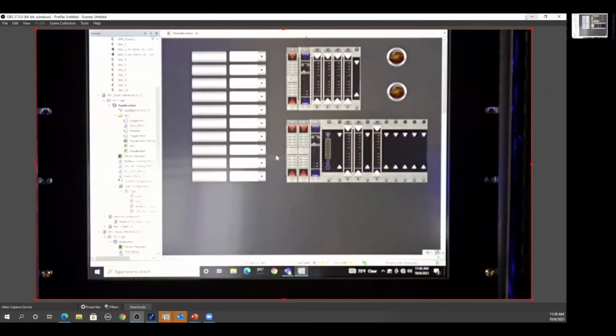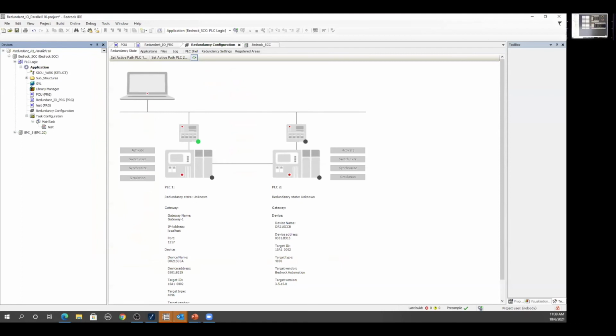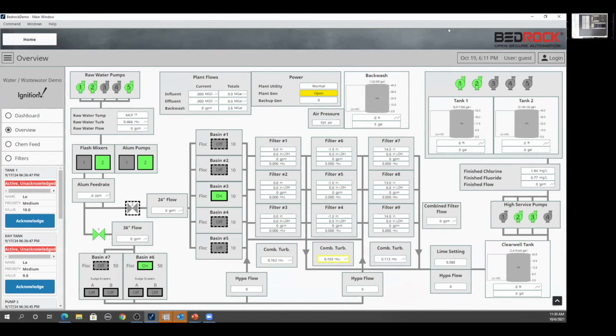Reinforcing what we talked about with SCADA communications, this is able to run local HMI visualizations while at the same time running a secure OPC UA connection up to Ignition in this case, or any of the major vendors, since they all support secure OPC UA. So you have the ability to bring this data into whatever SCADA provider you want, knowing it's secured, and this ends up being your centralized SCADA.